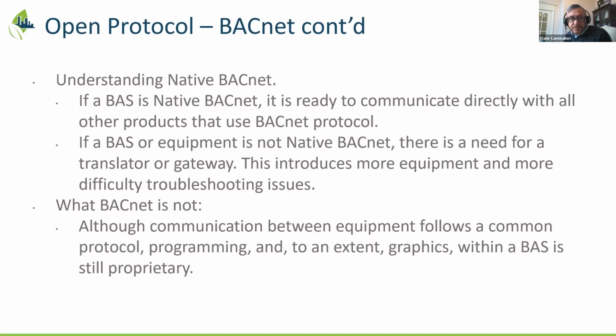What I want to highlight too is what BACnet is not. There's a perception that because equipment communicates on a common protocol, programming and graphics within a BAS are also standardized, but they're still very much proprietary. So if you have a Siemens, Delta, or Reliable Controls system, they can communicate with each other in terms of reading data, but the inherent programming done within the actual panels and controllers remains proprietary. Nothing wrong with that, but we want to make clear that certain things still remain proprietary even with a common communication protocol.